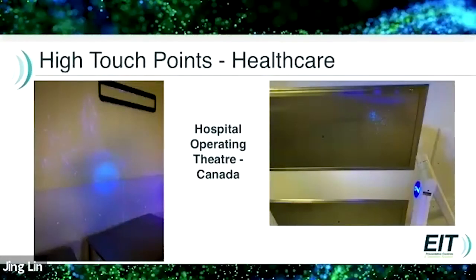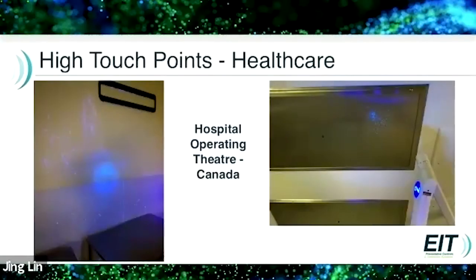This is a shot from a hospital operating theatre in Canada. There was a bin underneath the blue spot in the first picture, and this is where swabs were thrown off the wall and into the bin — those are the bits that got missed and splashed up the wall. On the right, there is a picture of the air conditioning system where bacteria are growing in the exit area and will probably get blown around the room.